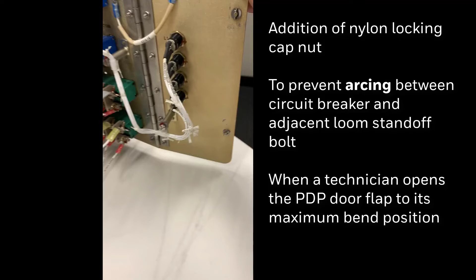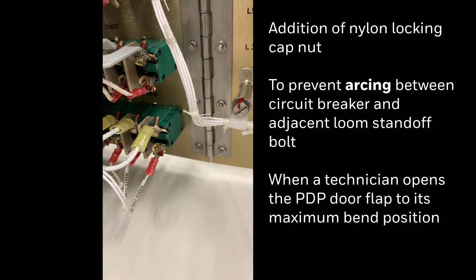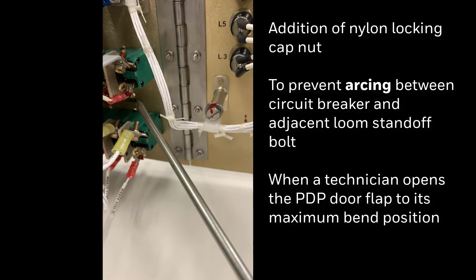Some maintenance actions are required to be performed with the panel supplied with power, and this is where the trouble occurs. So what we're looking at now is the offending circuit breaker that would have power, and this is what we need to protect against touching the standoff.